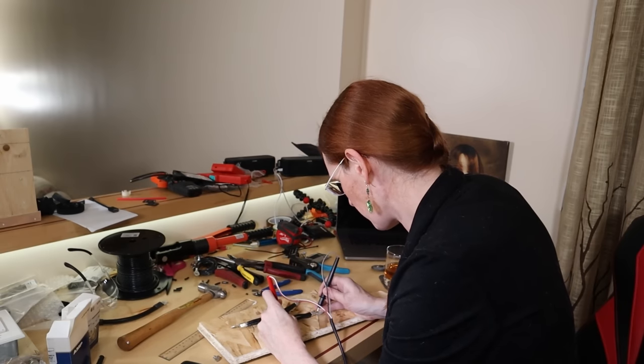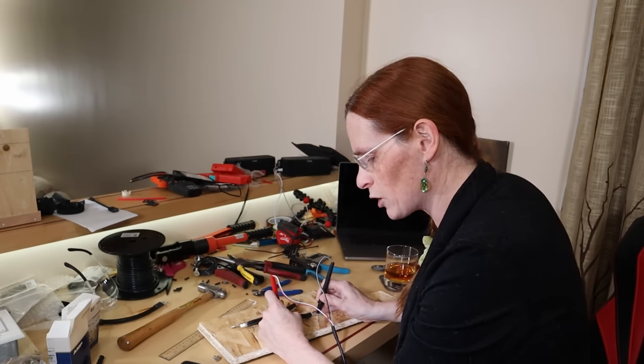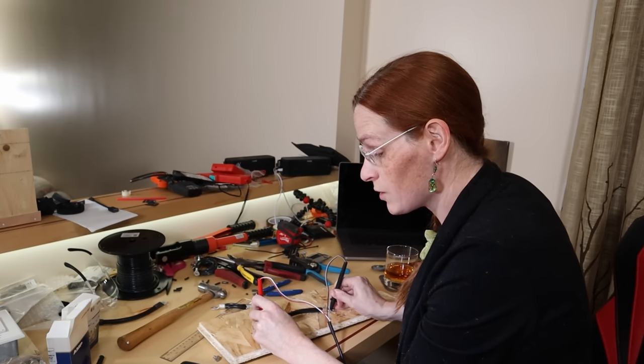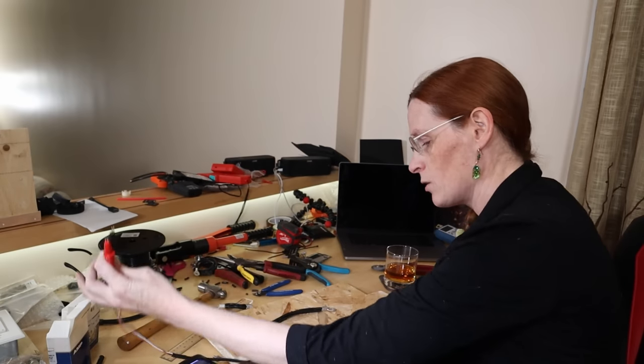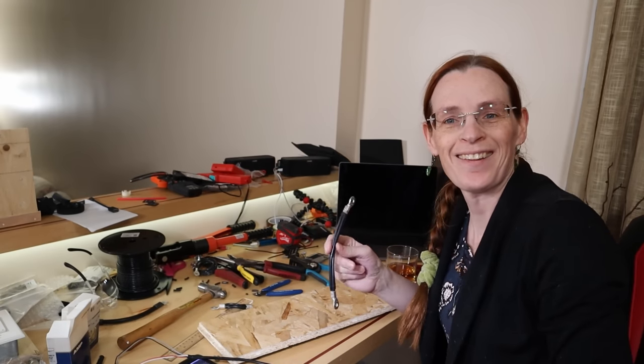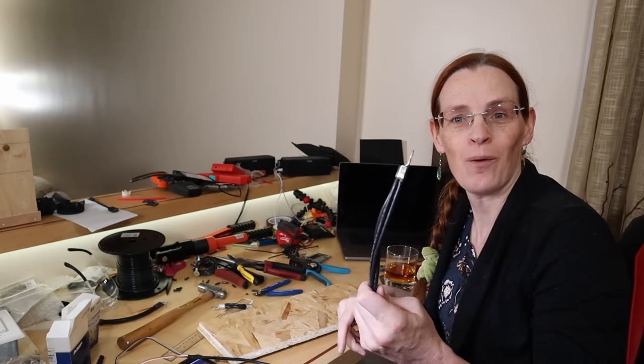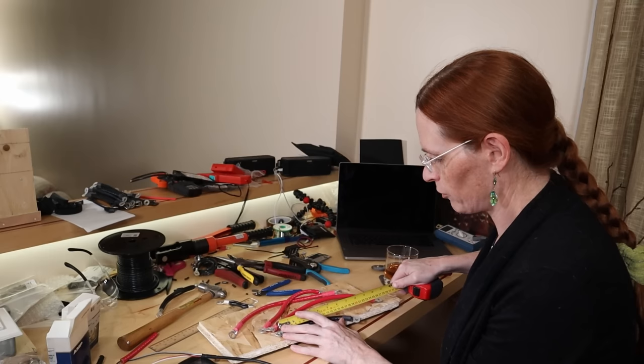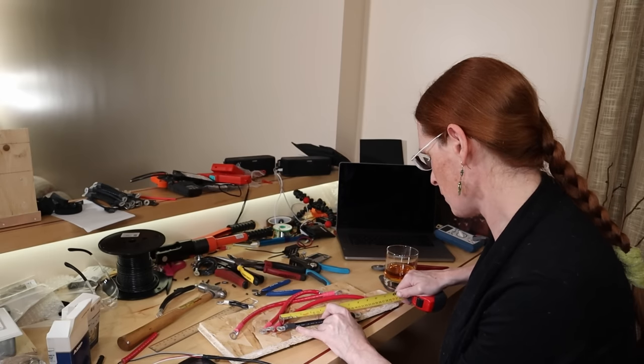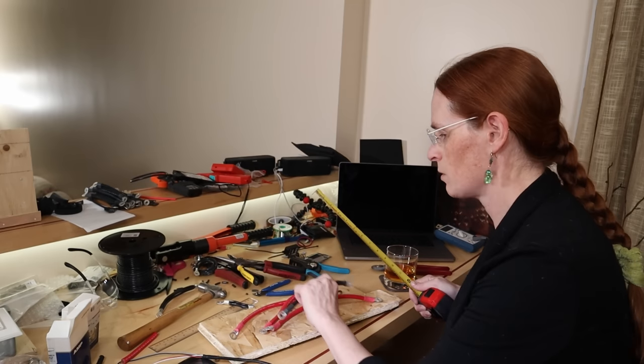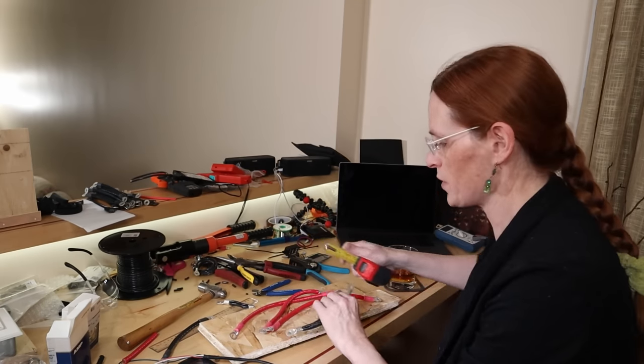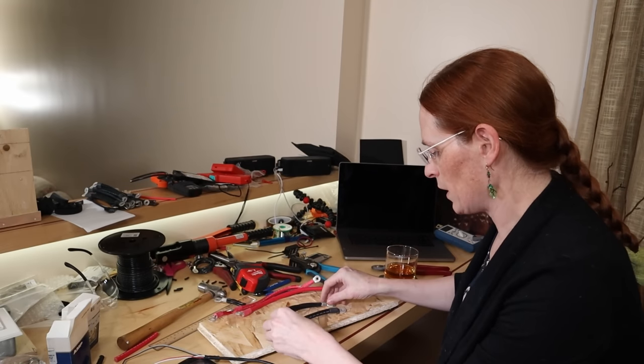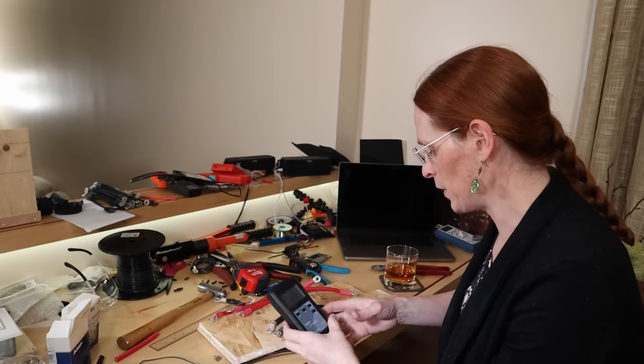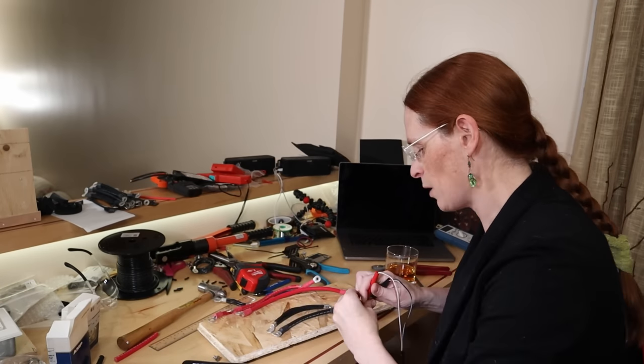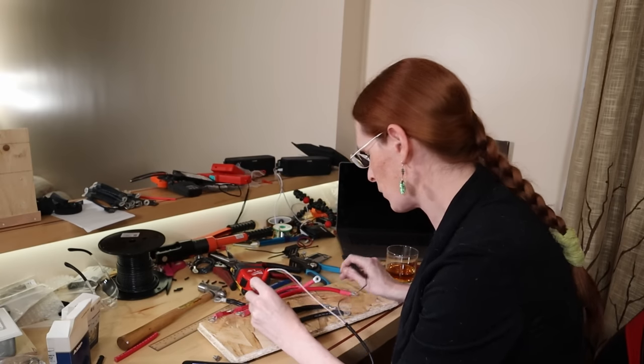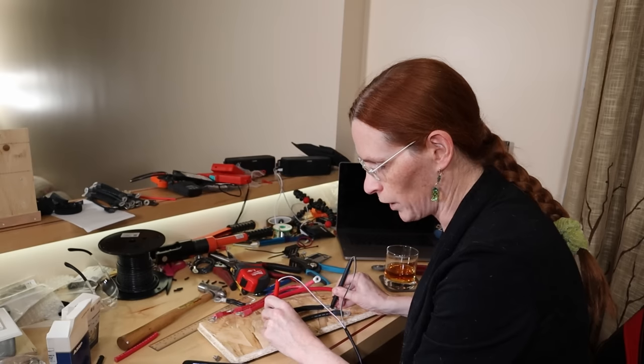The inside of the ring terminals of both: 0.07, 0.08, 0.15, 0.16. Okay, so it's the length — that's just how much resistance there is in the wire. This cable, measuring the actual cable distance, is about 17 centimeters. This one is about the same. So these two, despite being different — one a set of 4x10 gauge, one a single 4 gauge — their resistances should be about the same. 0.15, 0.16, 0.15, and holding.